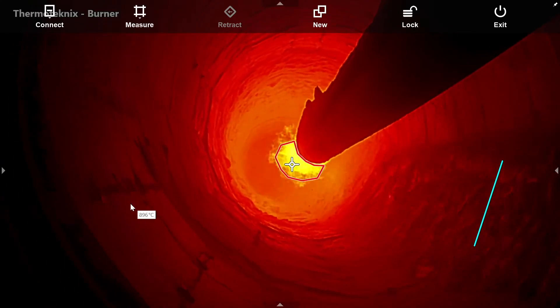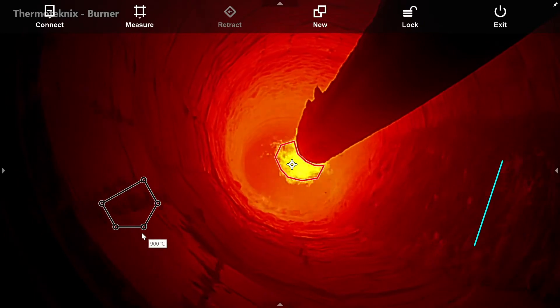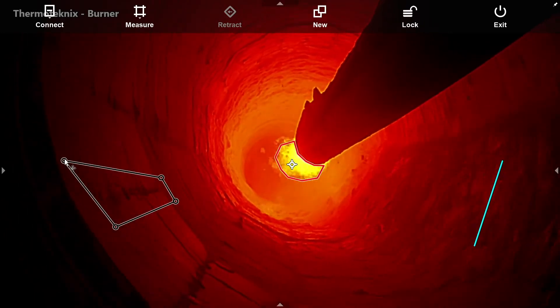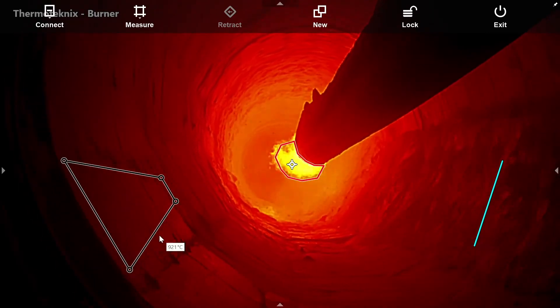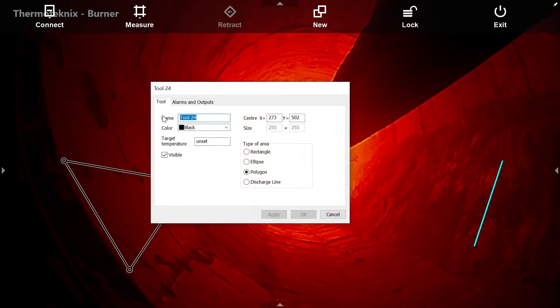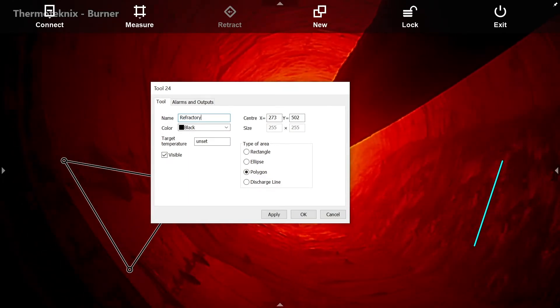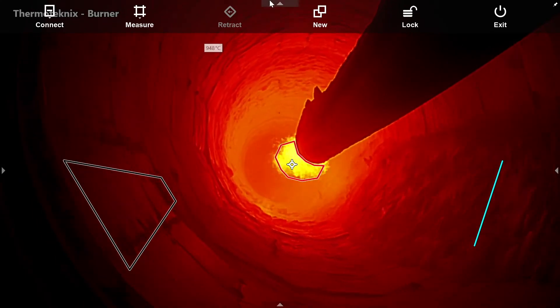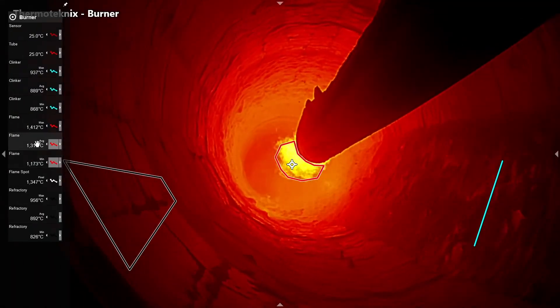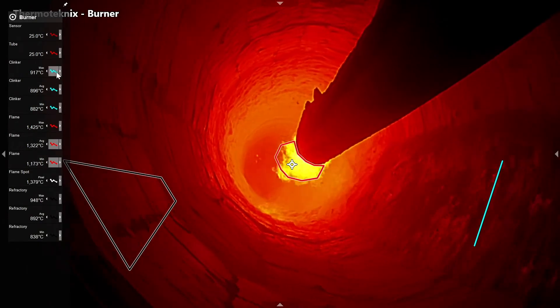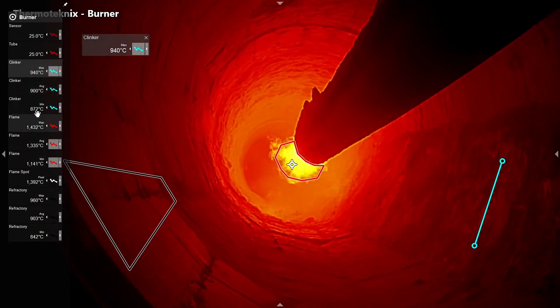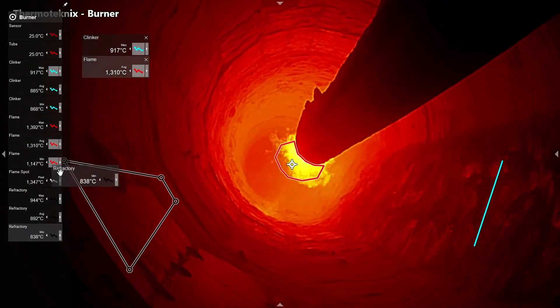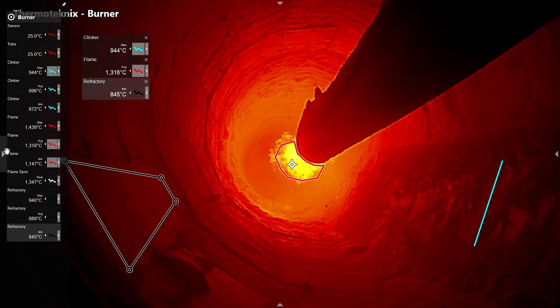You can add any number of measurement tools as spots, rectangles, ellipses, polygons or lines to define your regions of interest inside or outside on the kiln shell, on live data or on historic data. Tools can be customised with names and labels that can be dragged and dropped onto the screen at any time to display real-time maximum, average or minimum temperature values. Plotting data trends, live or historic, is as simple as clicking on its icon — the data is always there, ready for display or output.